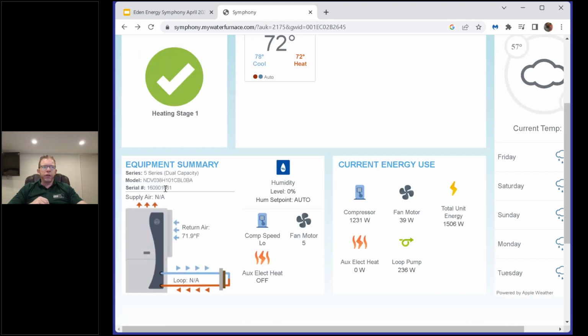If we scroll down on the left-hand side, we can see the equipment summary for this unit. This is a 5 series unit, a 3-ton unit, I can see that here where it says it's an NDVO 38. I can see it's currently running in low speed, the fan motor is in speed 5, and I can see what my return air temperature going back to that unit is. Over here on the right-hand side, I have the ability to see a lot more data.